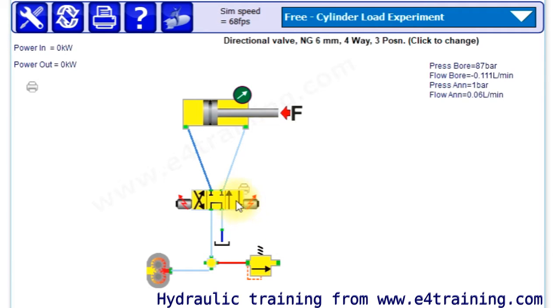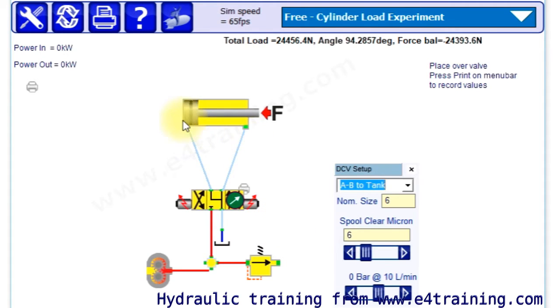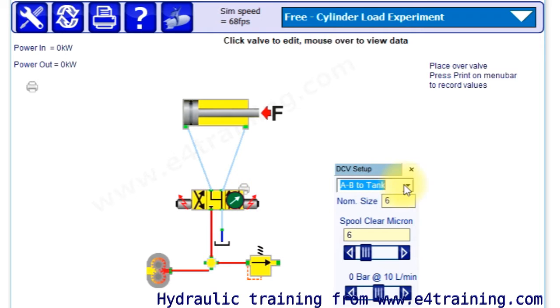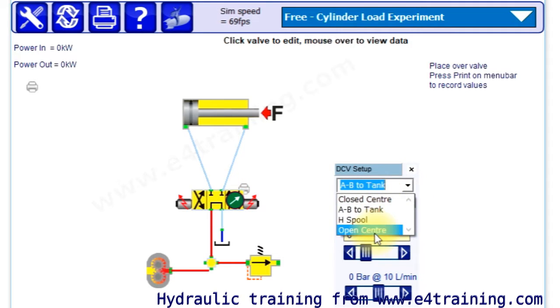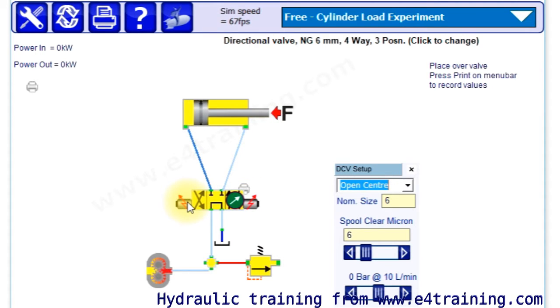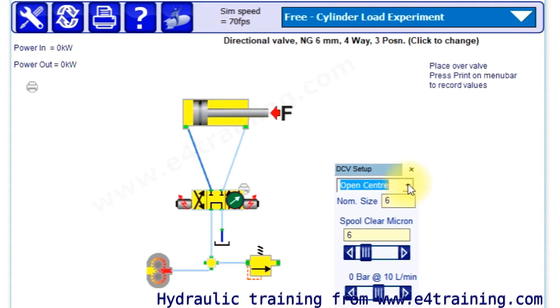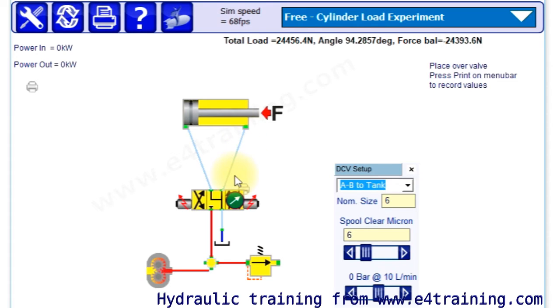We may like to change the center condition here, so we put A and B to tank. We've now got a less restricted center condition. If we had the closed or open center condition, there are restrictions there and there's still some leakage, and we could still get negative pressures in the annular side — even in that condition that may still cause damage depending on tank pressures. But if we select A-B to tank, we don't get any negative pressure.